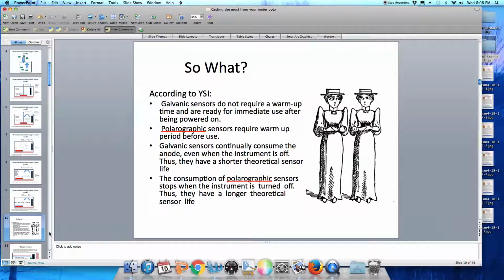According to YSI, the galvanic sensors do not require a warm-up time. Essentially, they are always on. As long as there's dissolved oxygen, or as long as there is oxygen from the atmosphere, for instance, undergoing reduction at the working electrode, and as long as the counter electrode is still providing electrons, the reaction will go. So the reaction is already going on when you turn the meter on. They do not require a warm-up time. Polarographic, on the other hand, do require a warm-up time before use.